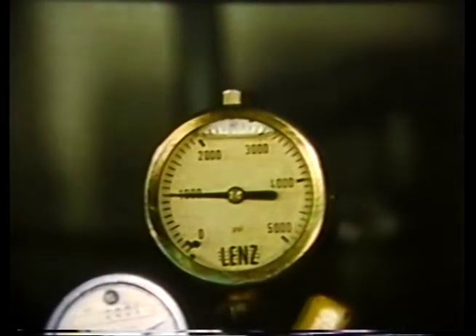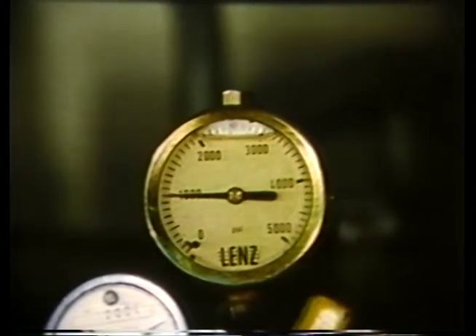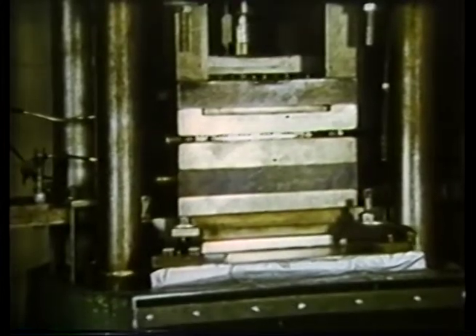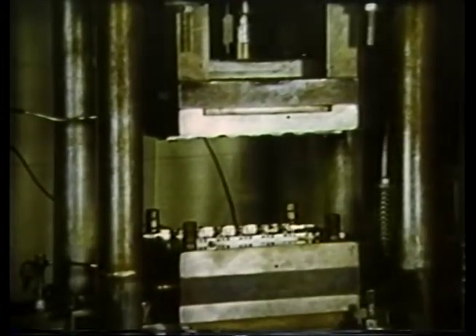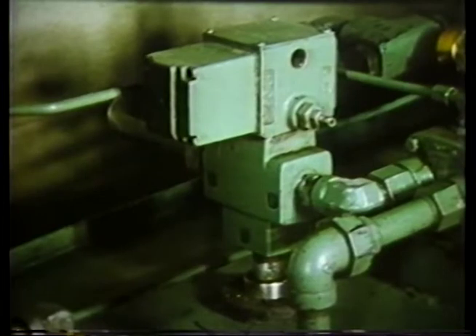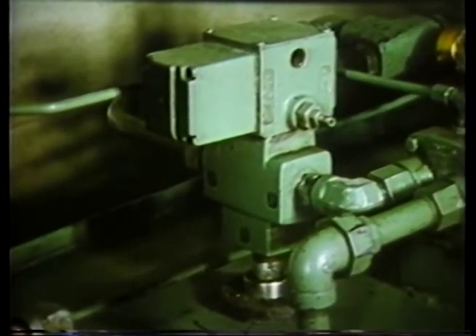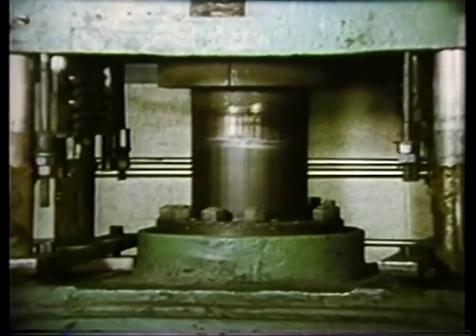The most usual sign of trouble in hydraulic systems is a loss of pressure somewhere beyond the pump, either gradual or abrupt. In addition to this possibility being observed on a pressure gauge, there will be loss of power from the work cylinder — it may stall or move more slowly than normal. Any component in the system may be at fault, but the three most likely trouble spots are the pump suction strainer, the relief valve sticking, or piston packing leaking.